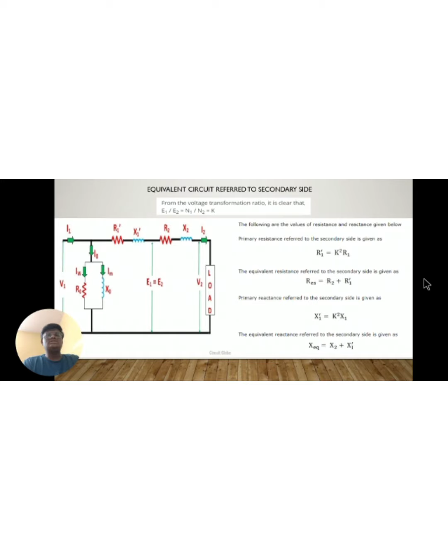The simplified equivalent circuit will be explained by Tushar. This is the simplified equivalent circuit of the transformer. No load current is hardly 3 to 5% of full load rated current. The parallel branch consisting of resistance and reactance can be omitted without introducing any appreciable error in the behavior of the transformer under loaded condition.